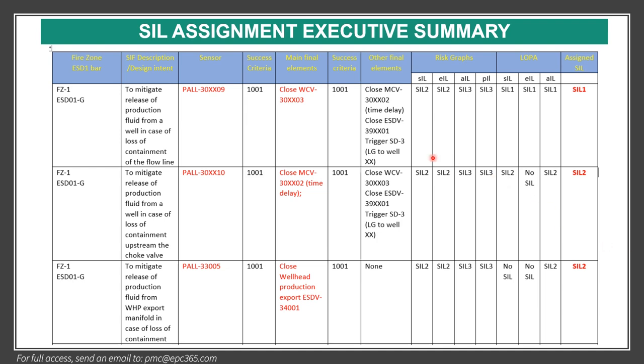When you have these things ready, you have to study the risk graph for safety, environment, asset, and production. If the SIL here is SIL 3, for example, and we are not sure about it, we do the LOPA analysis. The same applies for SIL environmental and asset assessments. Finally, from this process, we assign a SIL for this IPL, and this will be subject to verification or demonstration, which I will cover in another e-course.